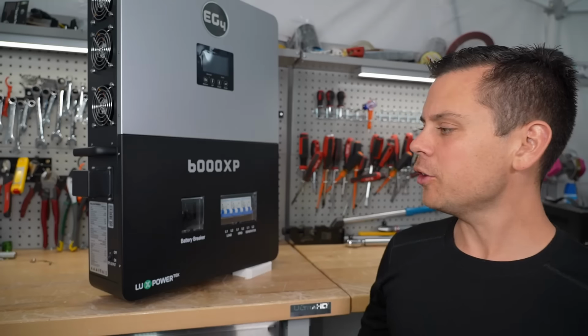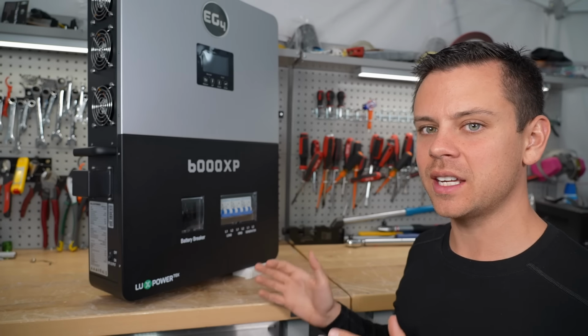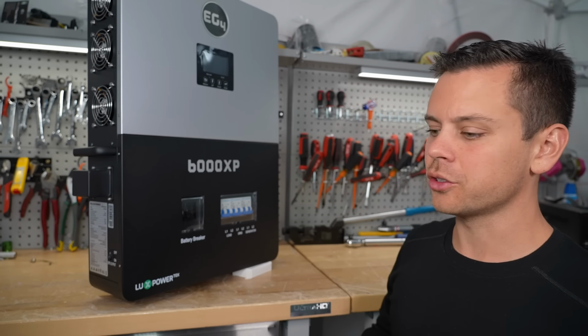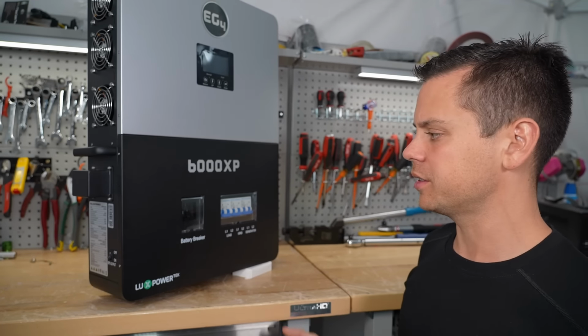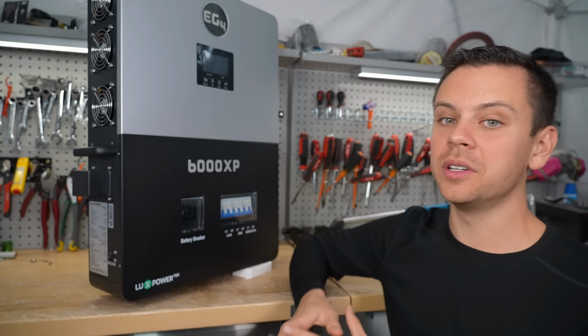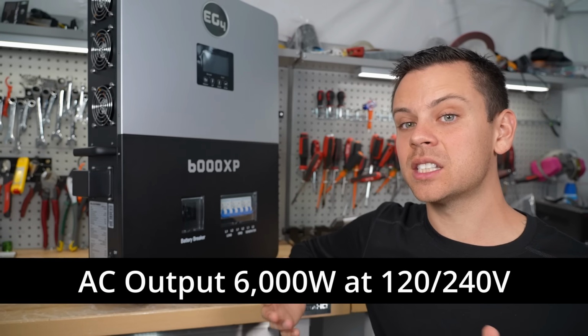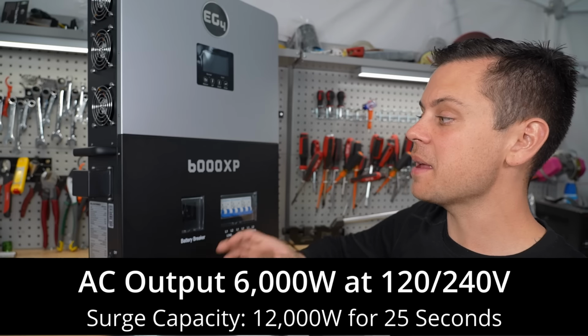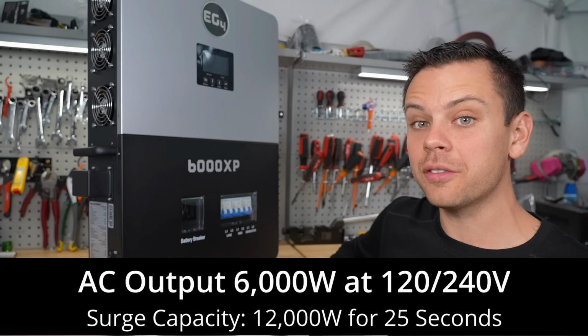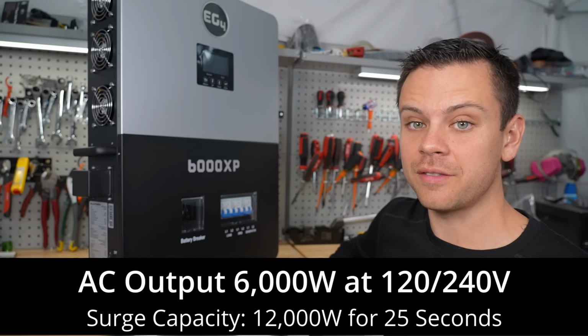Now let's talk about the basic functionality of this unit, the inverter, the solar charge controller, and everything else. First off, the inverter can output 6,000 watts, but that's in a split phase configuration, and it has a massive surge capacity of 12,000 watts for 25 seconds.